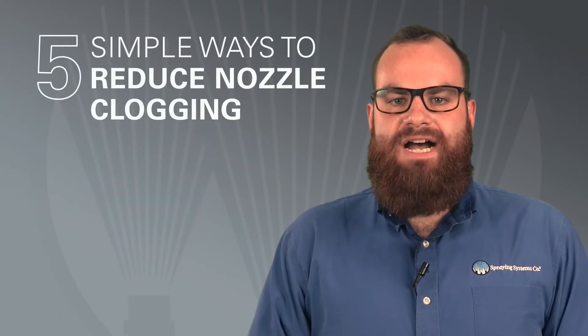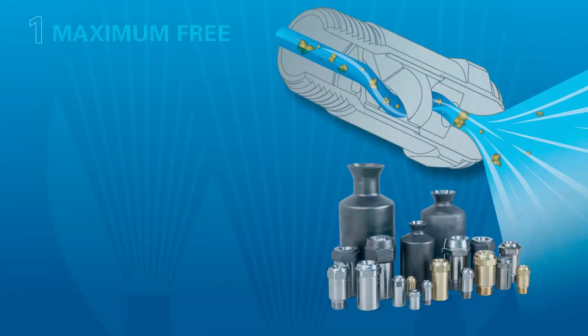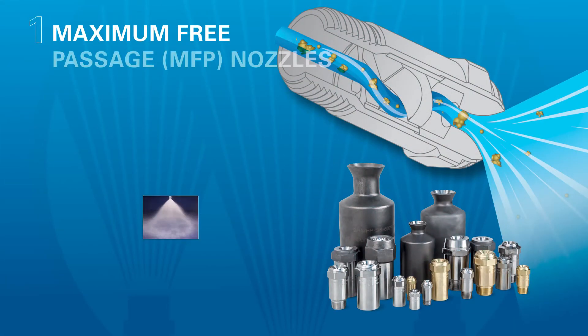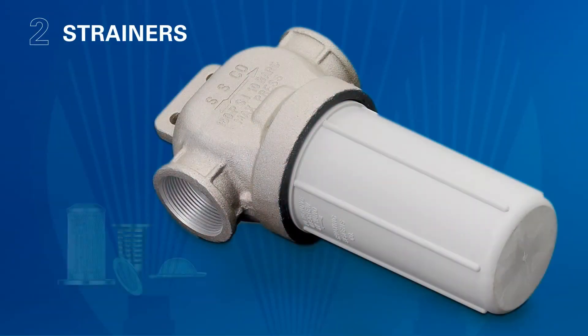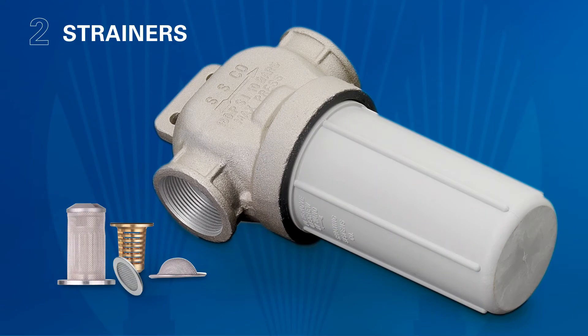There are five simple ways to reduce nozzle clogging. One, use maximum free passage nozzle designs. These nozzles offer open fluid passages that allow most contaminants to pass through. Two, add strainers. Strainers will trap larger particles and prevent debris from entering the spray nozzle orifice or the vane. Strainers are available in two forms, integral and T strainers.